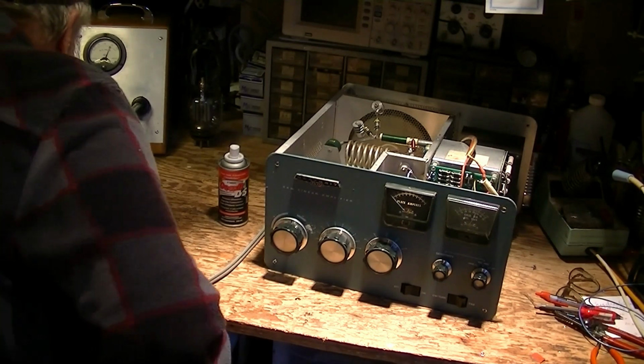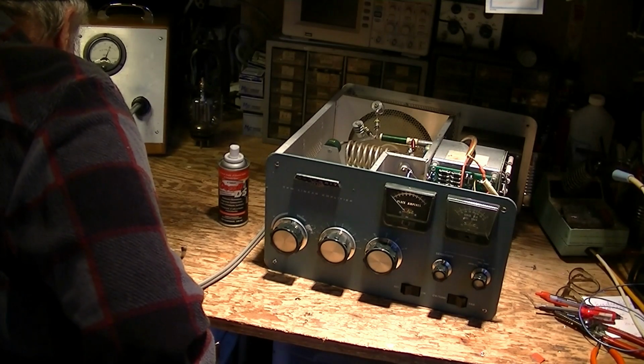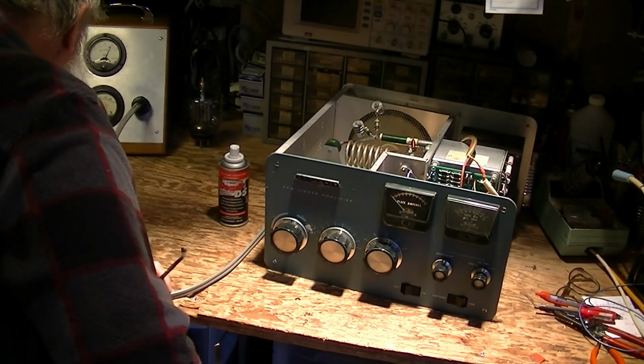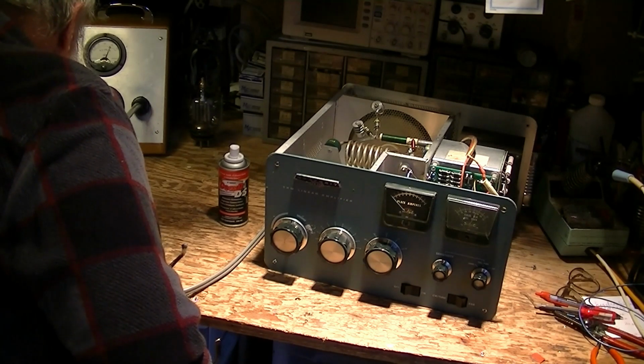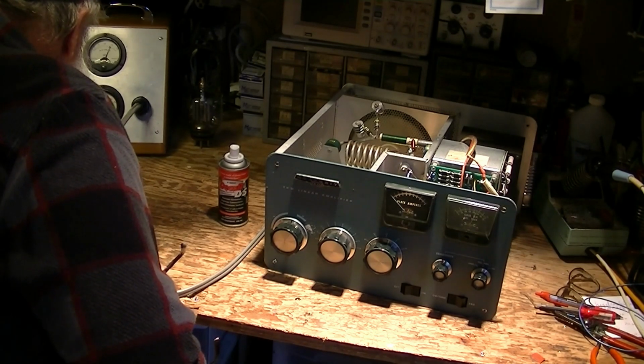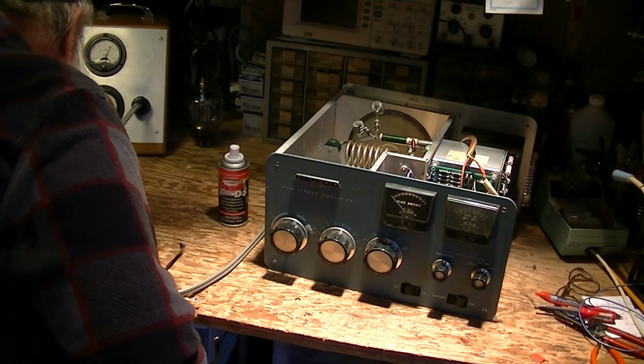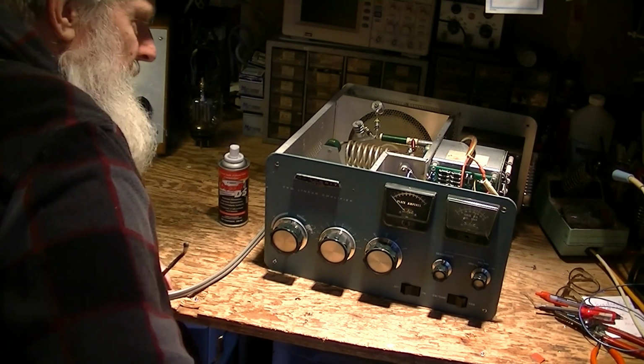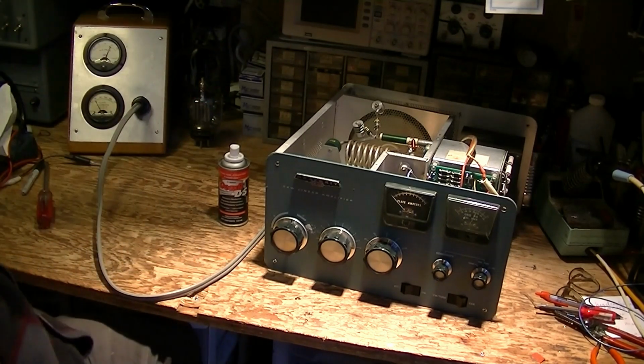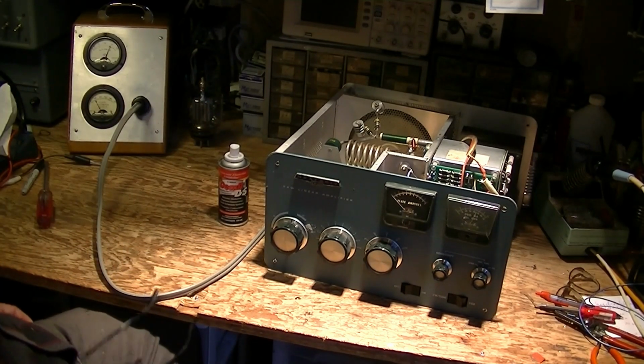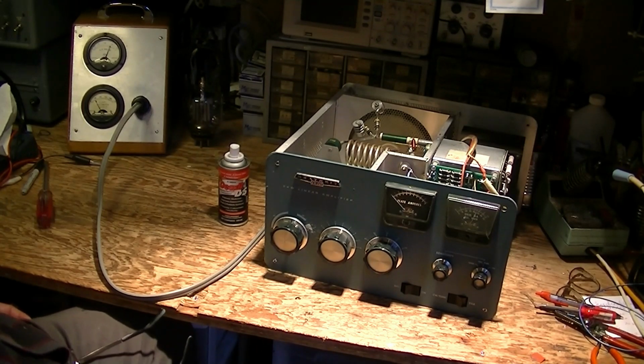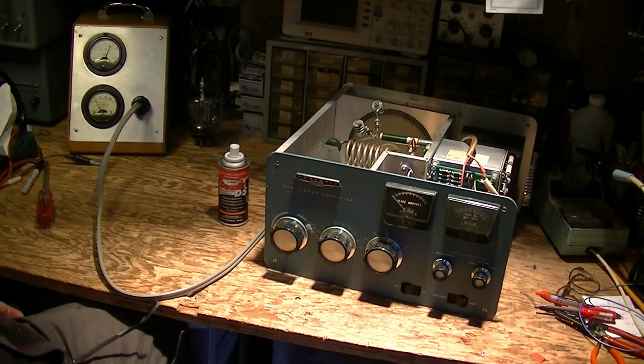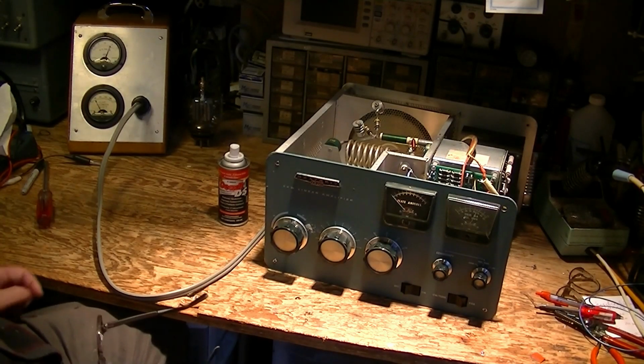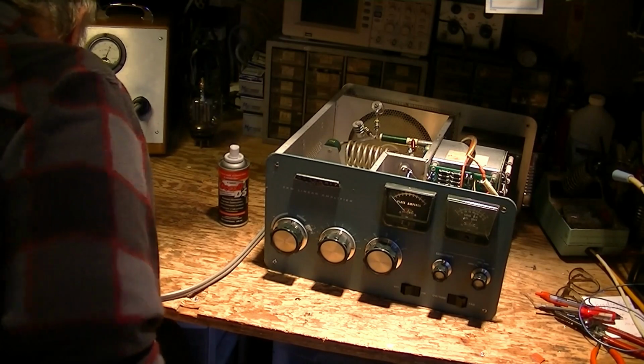Now we are up to 140 watts of draw here, and that was 75 or 80 for the power supply, so that's another 70 or so for this tube filament. Remember I said they draw 15 amps a piece, 30 amps for the pair of them, which is about 300 watts, so I don't know, this seems pretty minimal.